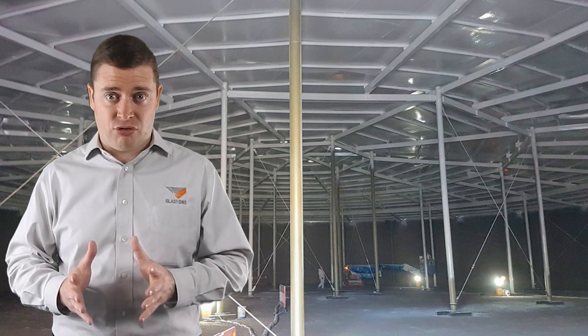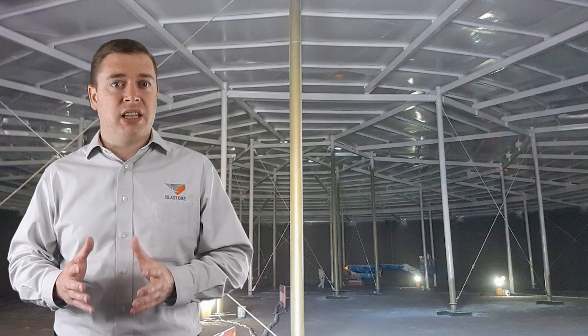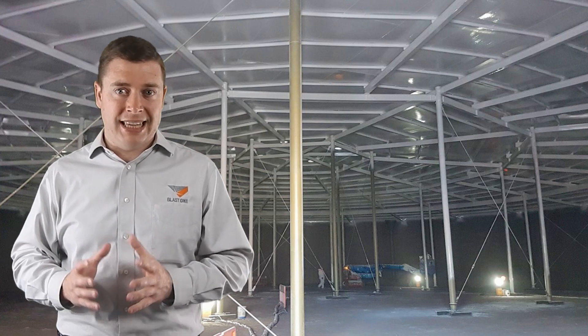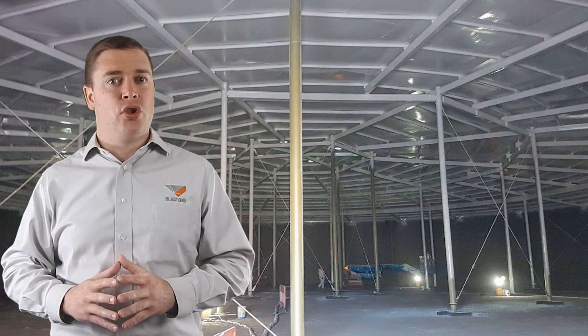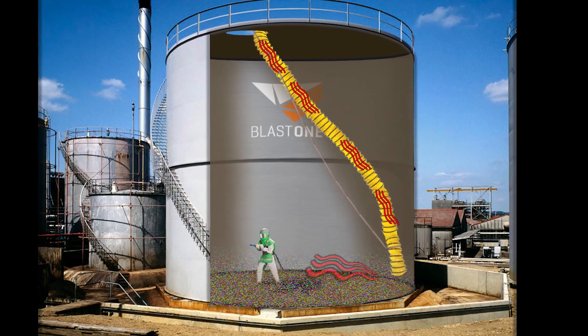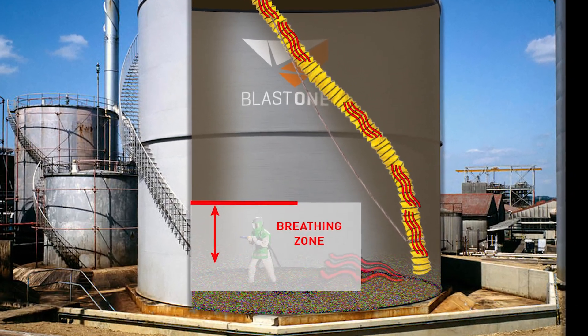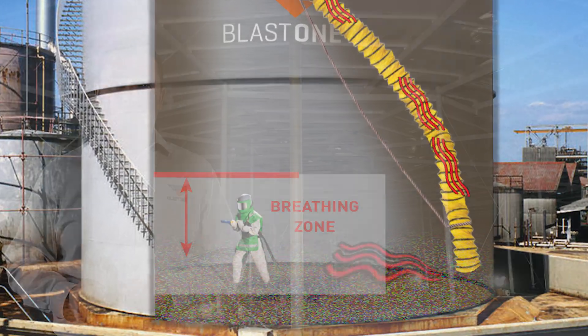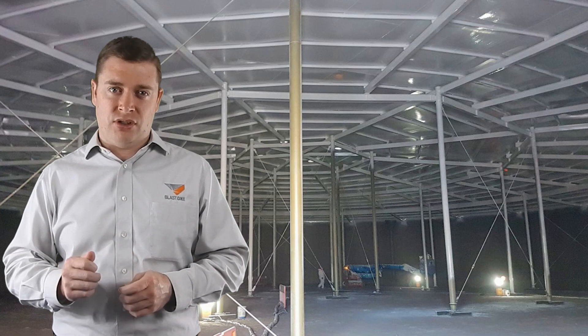When your ventilation method employs negative pressure — vacuum extraction — the ducting, although effective in the uppermost levels of the tank, isn't effectively drawing the heavy dust and gases that gravity concentrates towards the bottom of the tank. However, if we implement our strategy and the ducting is taken to the far back corner of that tank, it will effectively withdraw the dust away from the operator and extract the air through the ducting. These suggestions are general workaround tactics to give you an overview of how to manage dust in a single entrance tank project.